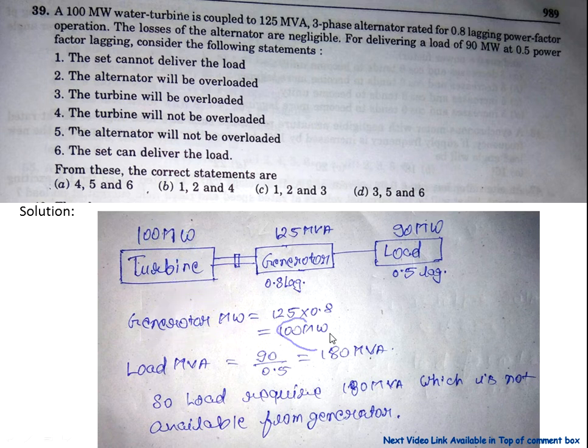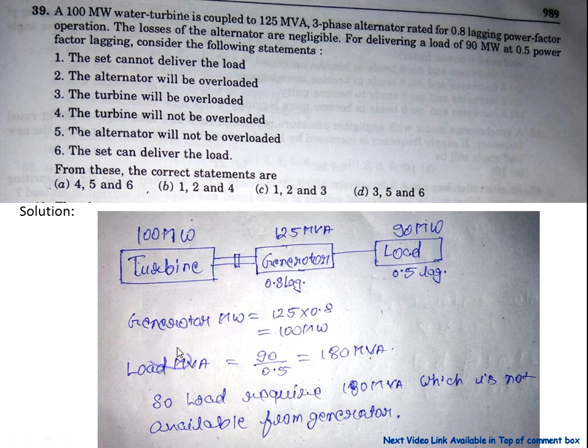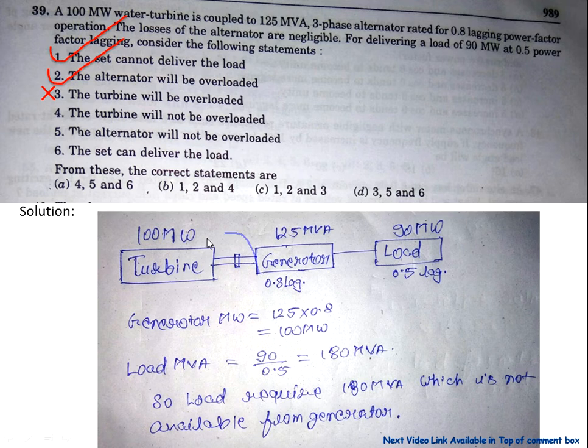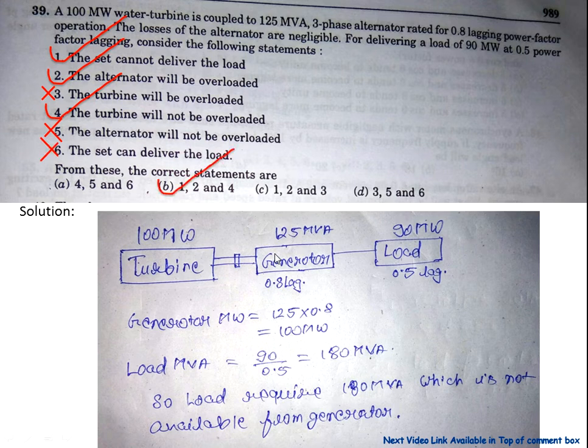The generator active power is 100 MW, which can be fulfilled by the turbine, so the turbine is not overloaded. However, the load requires 180 MVA but the generator is only 125 MVA, so the generator is overloaded and the whole set cannot deliver the power. Statement 1 (set cannot deliver power) and statement 2 (alternator will be overloaded) are correct. The turbine will not be overloaded. So answer B — statements 1, 2, and 4 — is correct.